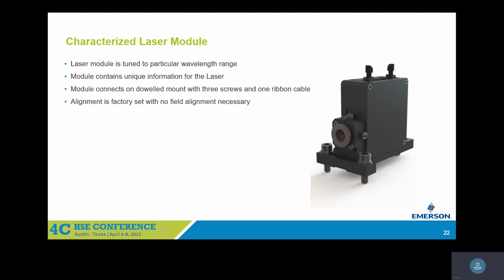So plug it in, let's say in 12 years, your CO laser needs to be replaced. Pull out your old CO laser, you put this one in, power it up, and number one, it's aligned. Number two, it says to the control board, I'm a CO laser. This is designed for it. And every laser is a little bit different, so we've corrected for that so that when you plug this in, it's getting the correct data. It additionally allows you to add different measurements later on. Let's say you don't have to measure SO2 initially, but you want to measure it later.